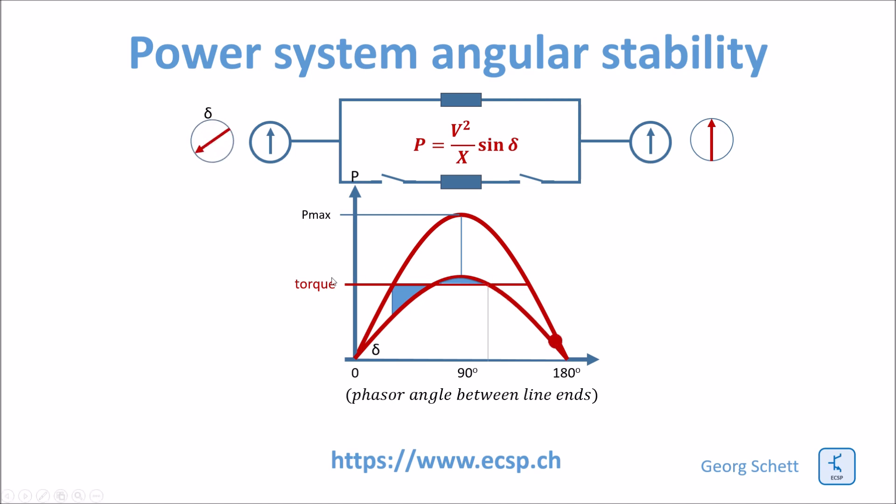So here you see now the relation, how these two triangles come into play. So we have originally selected a set point which was much too high. So the original angle was much too high for two lines in parallel, because we have always to consider the risk of losing one of the parallel lines.